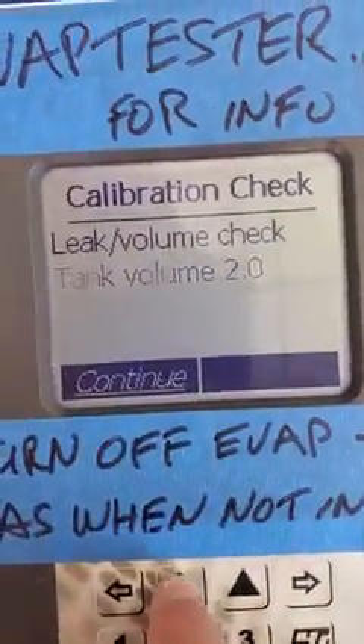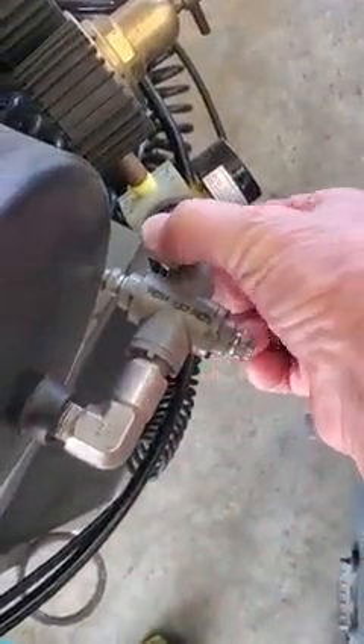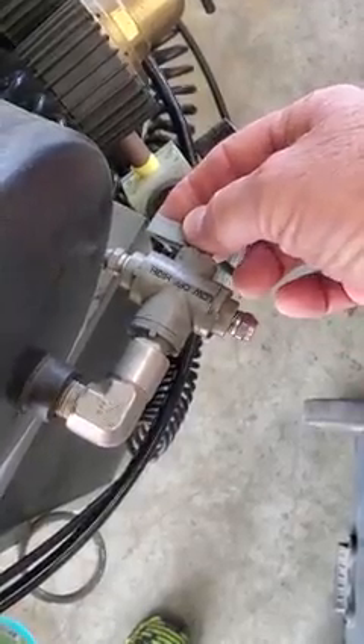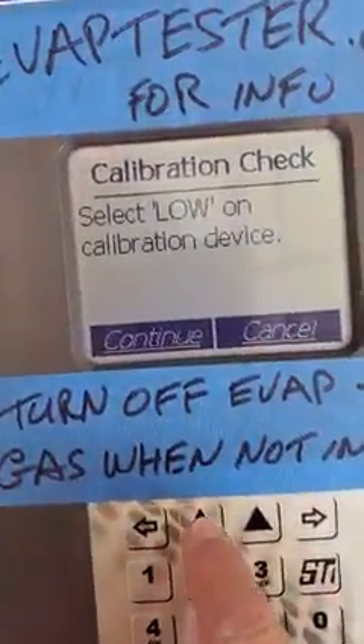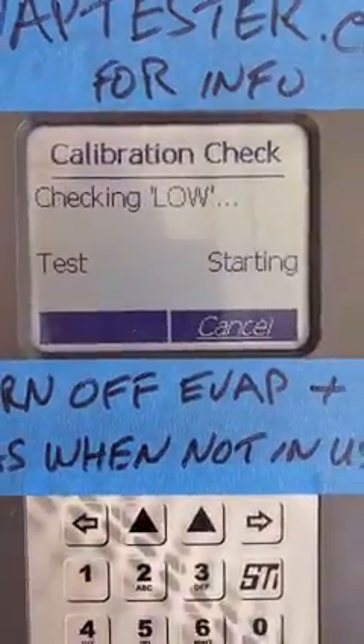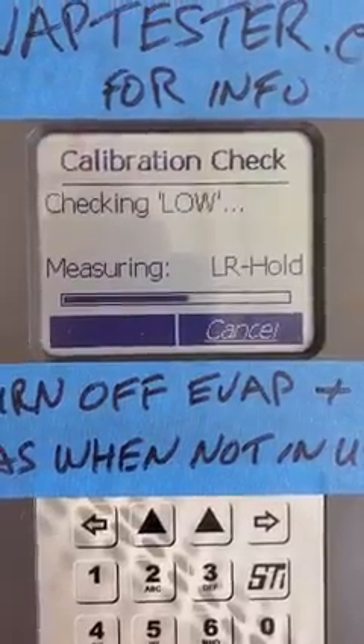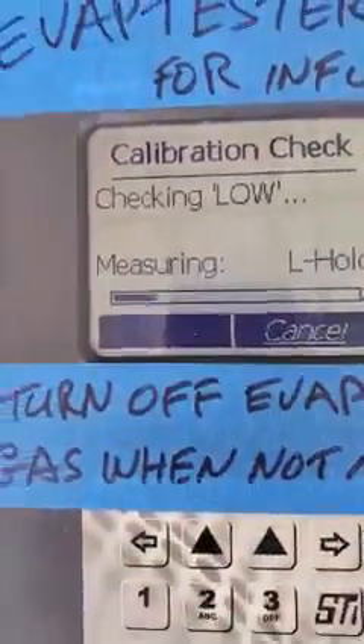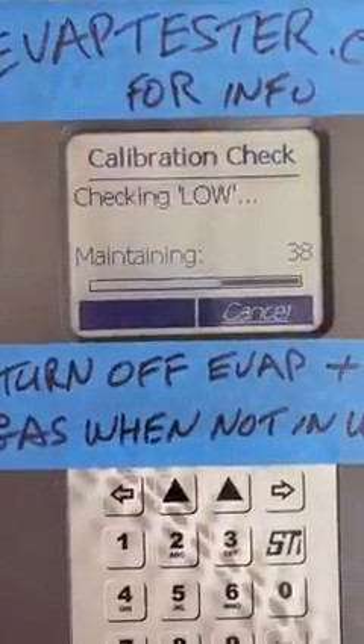So we will push continue to carry on with the calibration. Turn the valve to high for a couple of seconds to let the tank breathe, then turn it to low and start the low calibration. Alright, so as you can see, it's doing the low part of the calibration. Your black hose is on the tank and your valve is set to low.